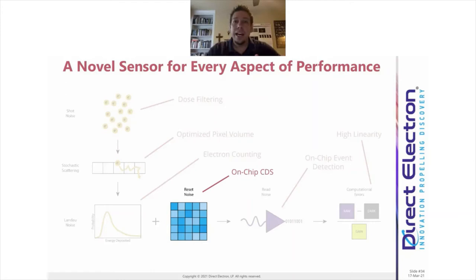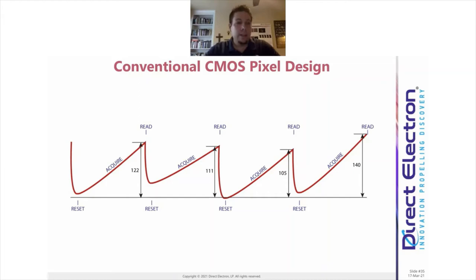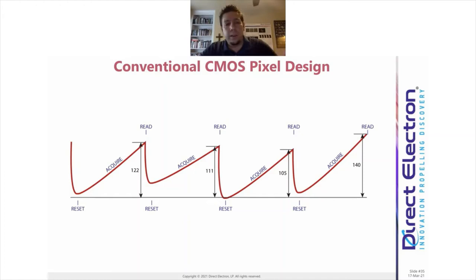The second optimization was decreasing the false positive rate. We want to detect every electron hitting the sensor without picking up background noise. Ideally, with the beam off, you'd get essentially black images — as few false positives as possible. One way we achieve this is with correlated double sampling. A conventional CMOS device works by resetting the pixel to zero, acquiring signal, then reading out — but the reset doesn't bring the pixel value exactly to zero; it leaves a noisy non-zero reset value that adds noise to the readout.